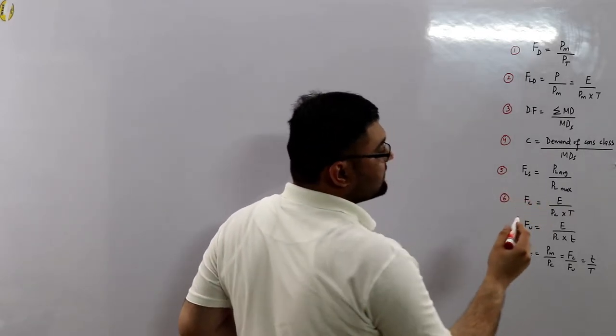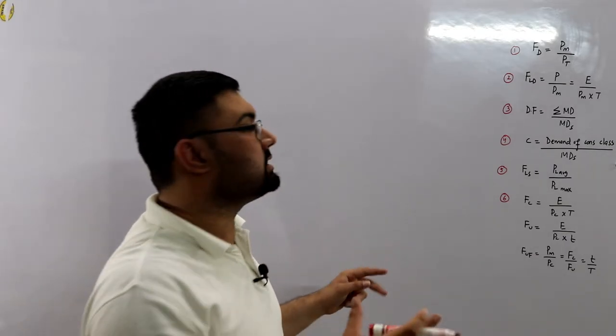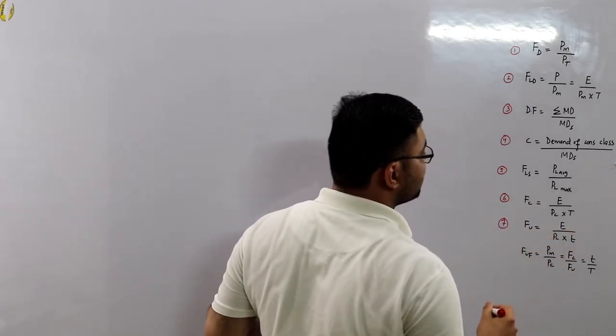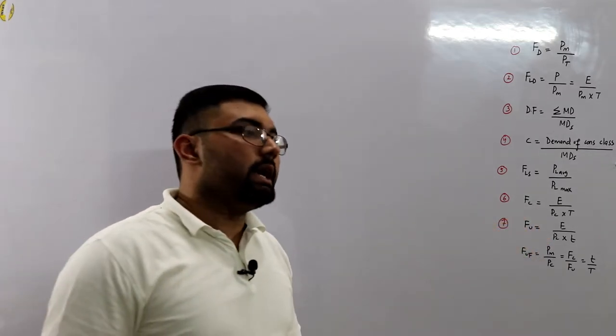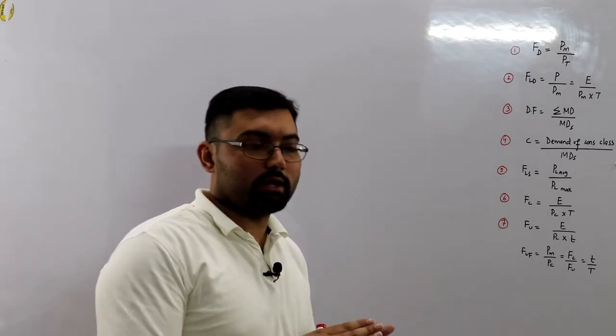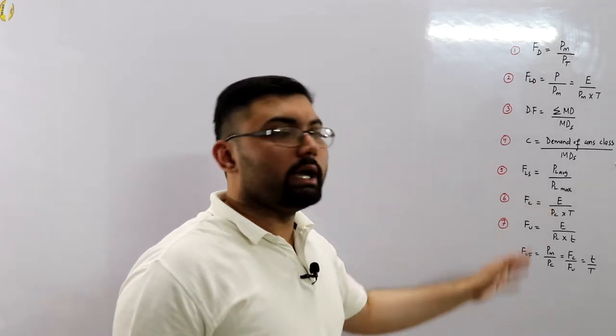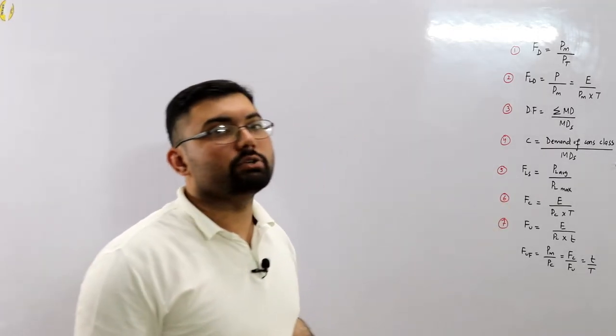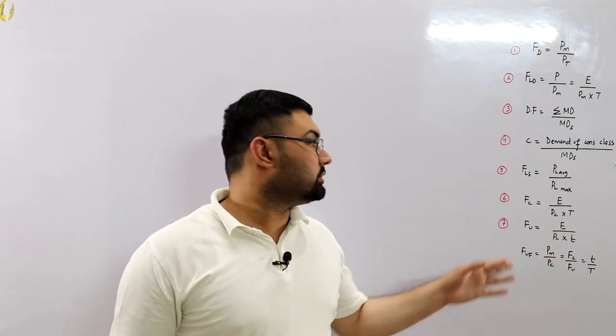Number six is the plant capacity factor — the energy units actually generated to the maximum energy units that could have been generated over a span of time. Number seven is the plant use factor — energy units generated divided by time, where that time is the time for which the plant is actually running, with shutdown and maintenance time removed. In the plant capacity factor, all those times are also included, as I have already explained. For instance, for a yearly capacity factor you include all hours in the year: 8,760.